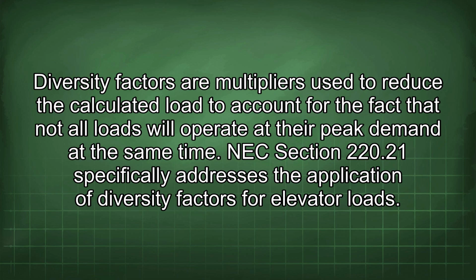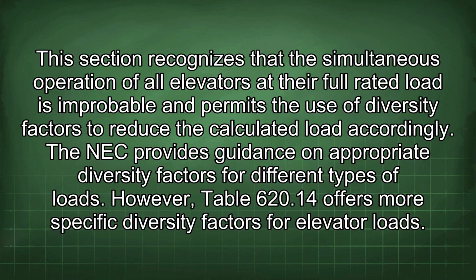NEC Section 220.21 specifically addresses the application of diversity factors for elevator loads. This section recognizes that the simultaneous operation of all elevators at the full rated load is improbable and permits the use of diversity factors to reduce the calculated load accordingly. The NEC provides guidance on appropriate diversity factors for different types of loads. However, Table 620.14 offers more specific diversity factors for elevator loads.